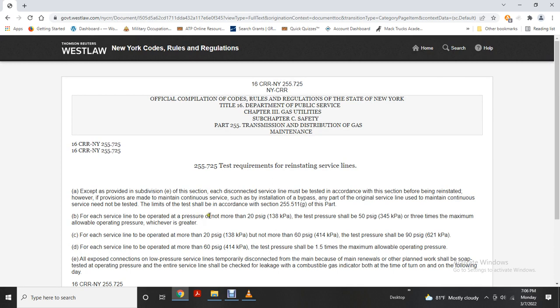For each service line operated at a pressure not more than 20 psi gauge, the test pressure is 50 psi gauge or 3 times the maximum operating pressure, whichever is greater. For each service line operated at more than 20 psi gauge but not more than 60 psi gauge, the test pressure should be 90 psi gauge.